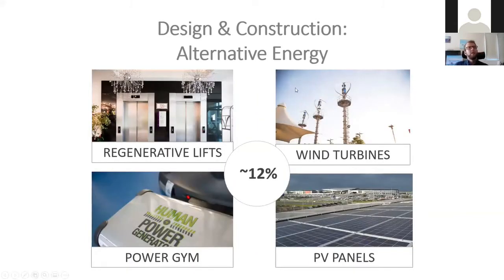Some of the interventions on the alternative energy side: what we're looking at on the top left here is regenerative lifts, which at the time was the first installation on the African continent. In essence, when gravity is doing the work for the lifts—when the cabin is full and traveling down, the cabin with occupants is heavier than the counterweight, or when the cabin is empty traveling up, the counterweight attached via a steel wire is heavier and wants to pull the cabin up—in those two conditions gravity is doing the work. That effect of gravity is harnessed through the drive motor, which acts as a generator, and roughly 30% of the input energy is harnessed and inserted back into the building's grid.